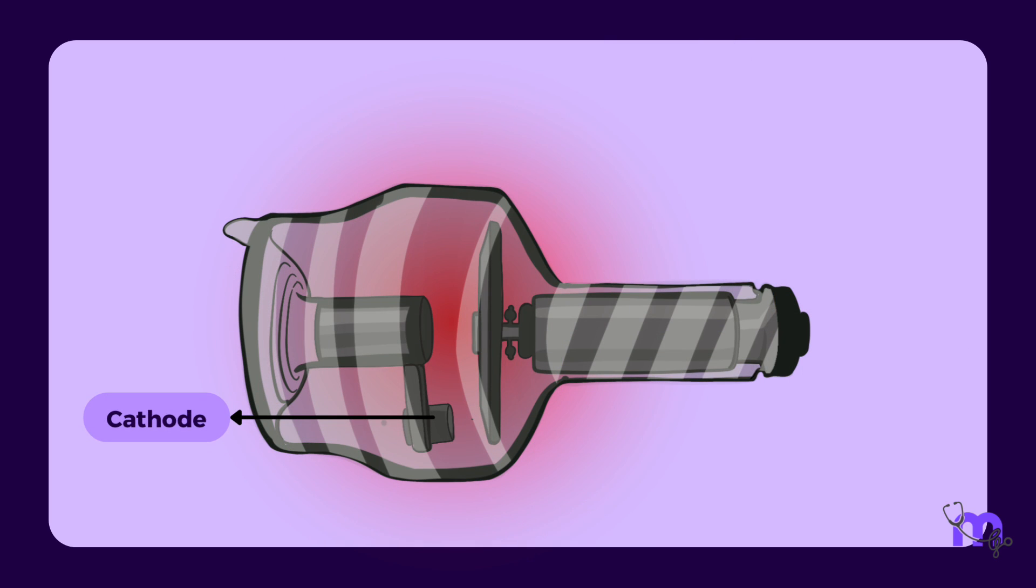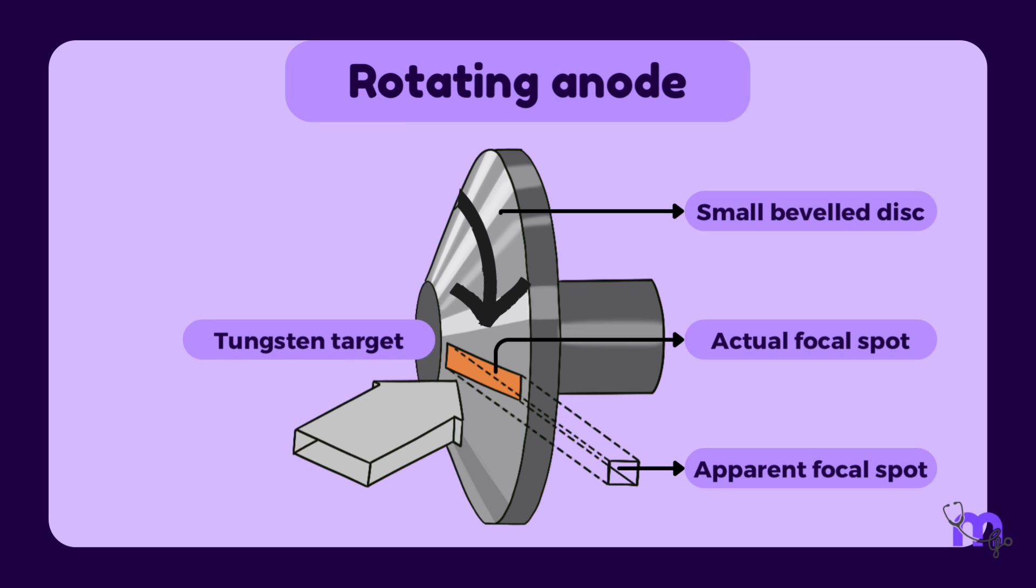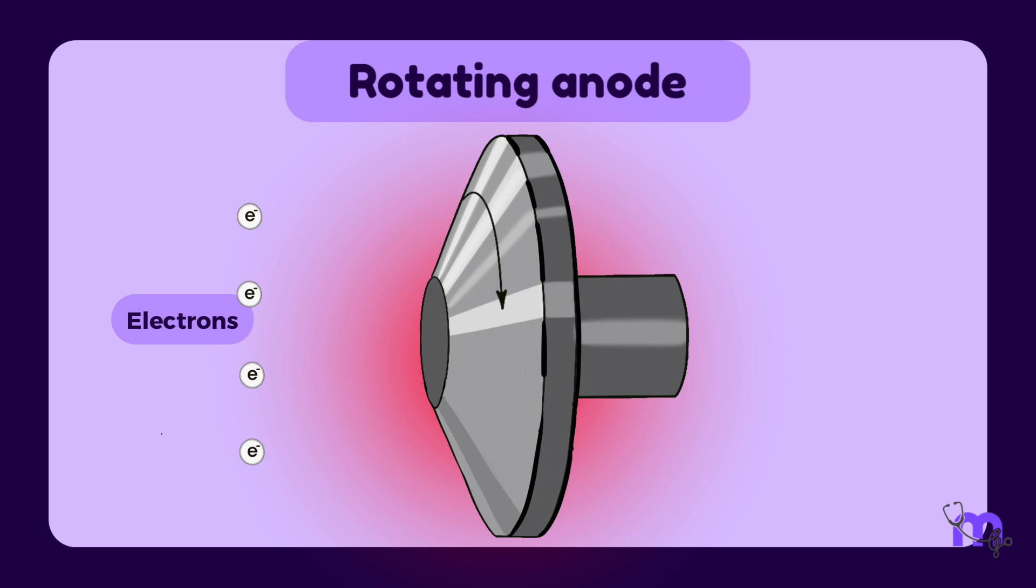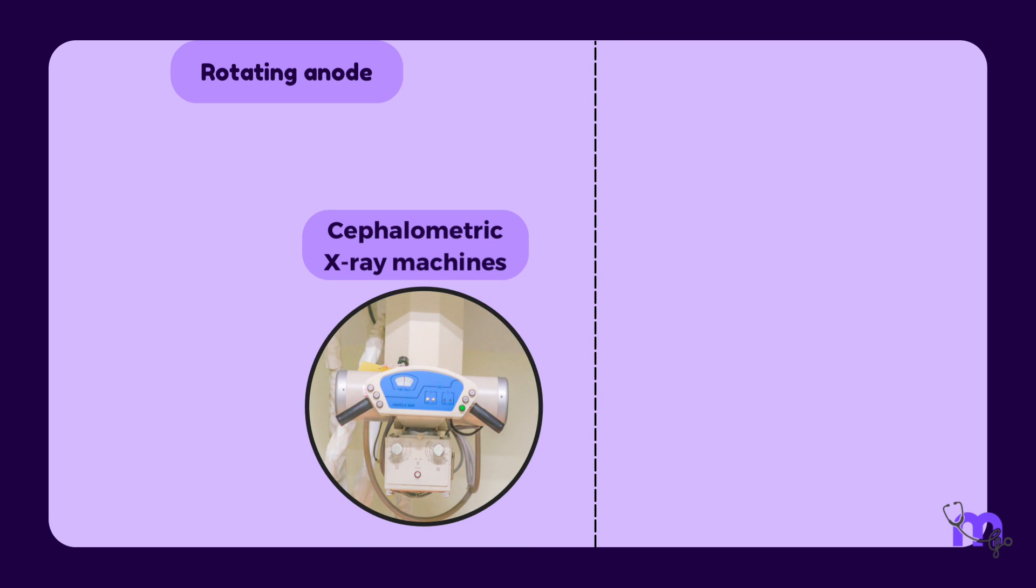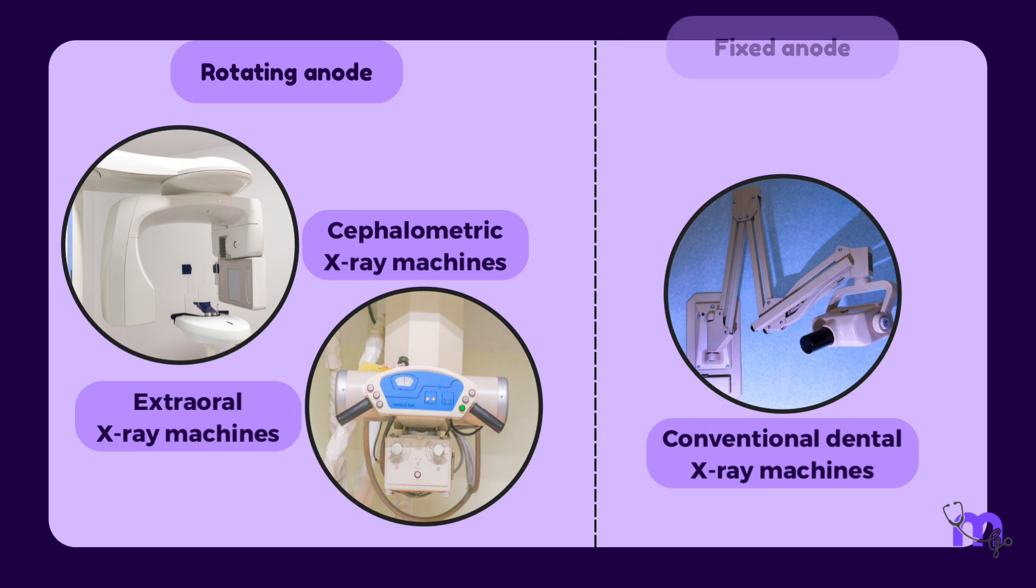Another method of dissipating heat from a small focal spot is to use a rotating anode. In the rotating anode, the tungsten target is in the form of a small beveled disc that rotates when the tube is in operation. As a result, electrons strike successive areas of the target and heat gets dissipated over a large area. Such rotating anodes are not used in conventional dental X-ray machines but may be used in cephalometric or extraoral X-ray machines. Conventional dental X-ray machines use fixed anodes that stay stationary while in function.